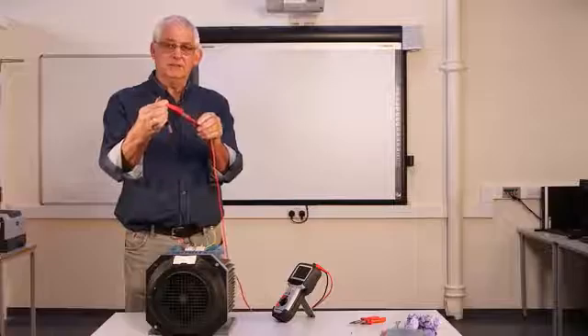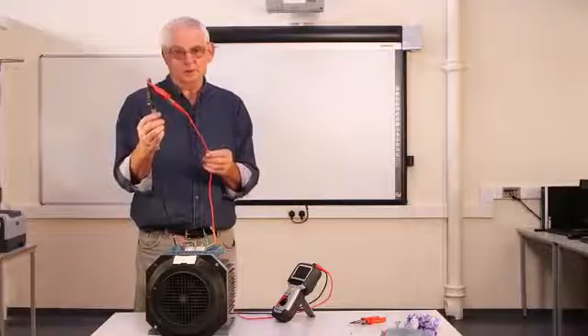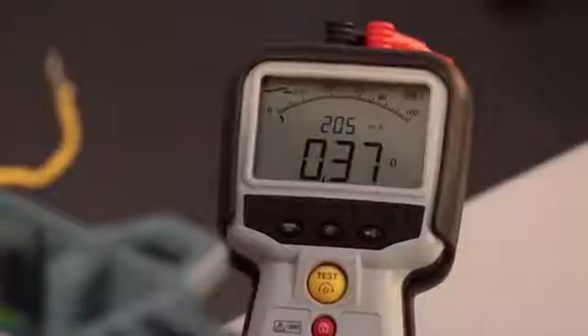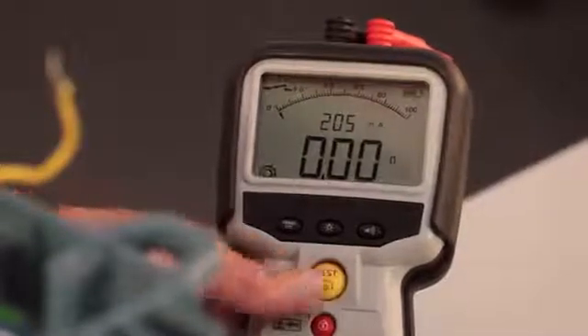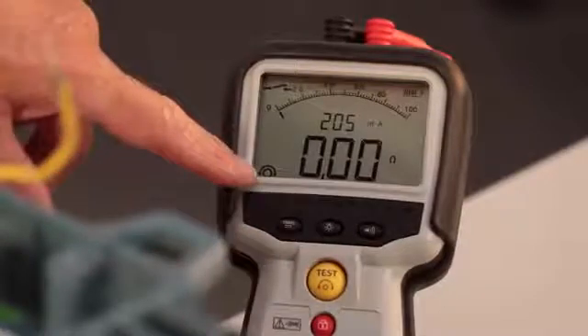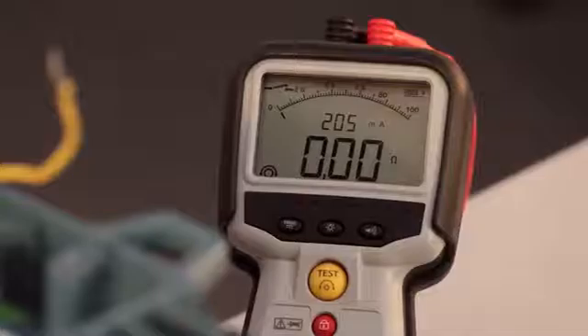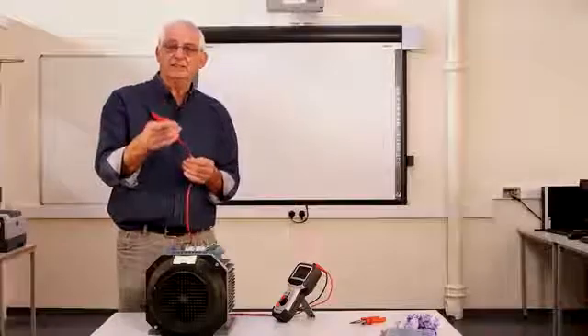Push the ends together as tightly as you can just to make sure you've got a good connection, and if there's any dirt or anything inside the crocodile clips you push through that. With this instrument we can see that these leads have got a resistance value of 0.37 of an ohm. If I just push the button to zero it, there's a little symbol comes up in the bottom left hand corner that tells me that the instrument is now zeroed and any measurement I take will be less the value of the leads.